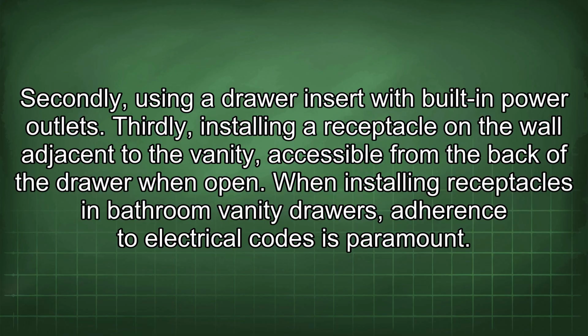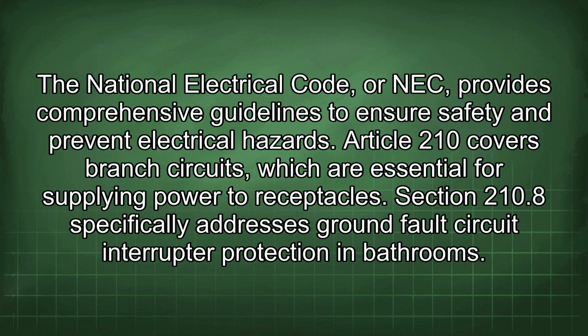When installing receptacles in bathroom vanity drawers, adherence to electrical codes is paramount. The National Electrical Code, or NEC, provides comprehensive guidelines to ensure safety and prevent electrical hazards. Article 210 covers branch circuits, which are essential for supplying power to receptacles. Section 210.8 specifically addresses ground fault circuit interrupter protection in bathrooms.